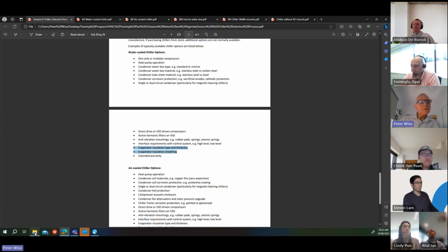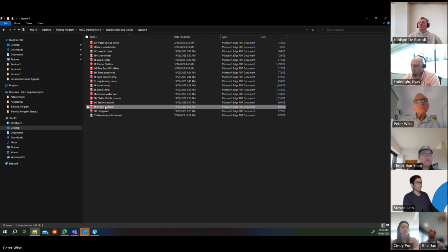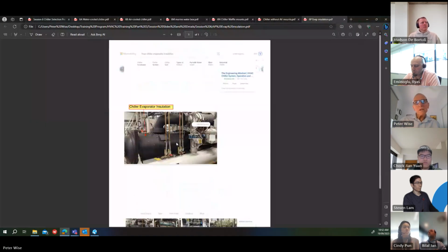Materials available are closed cell material like Armaflex, kind of a rubbery material. That's the standard that they put on evaporators. But you can get polystyrene or possibly polyurethane if you want a higher level resistance. But as a standard, Armaflex is normal, and you can get that sheath as well.